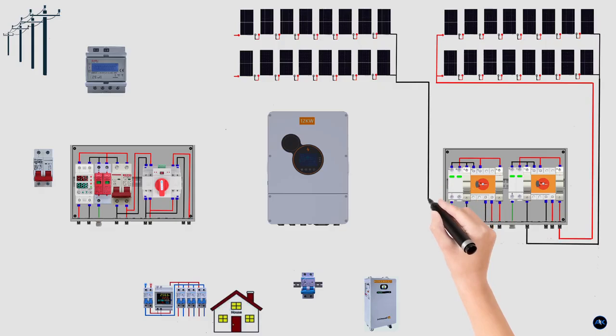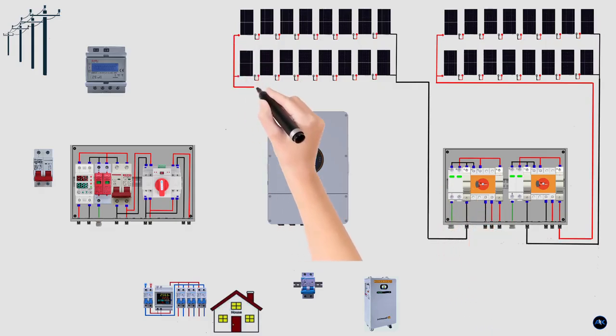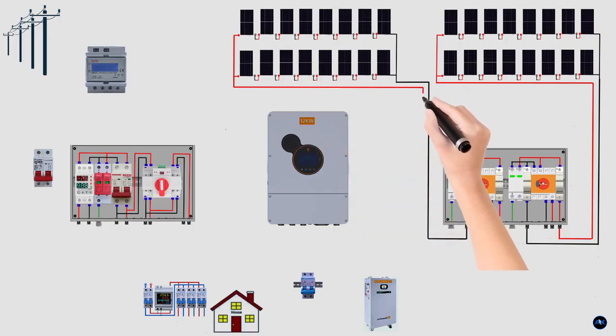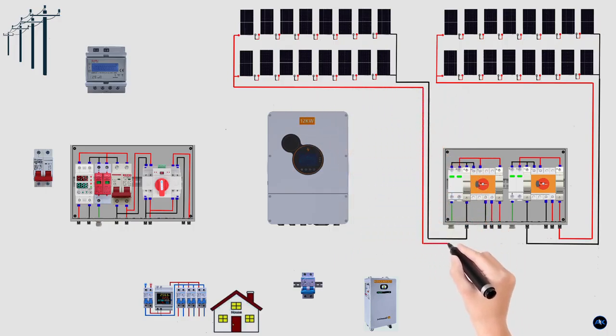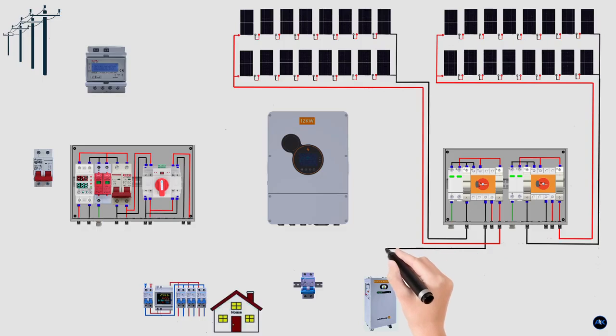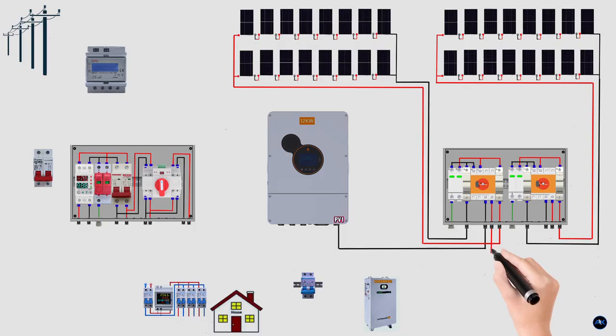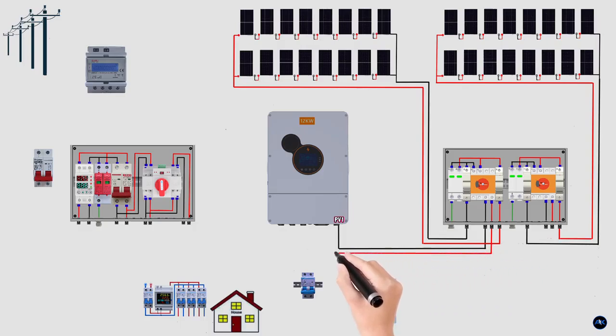We make 2 identical strings like this. These 2 strings are then connected in parallel so the voltage stays the same, but the current increases. This parallel connection is done using a string combiner or MC4Y connectors, depending on the system design. Before the solar power enters the inverter, each string must pass through a DC fuse. These fuses protect the system if one string develops a fault and tries to send current backward into another string.